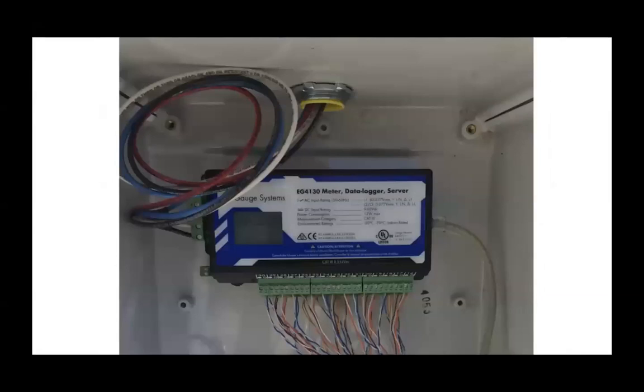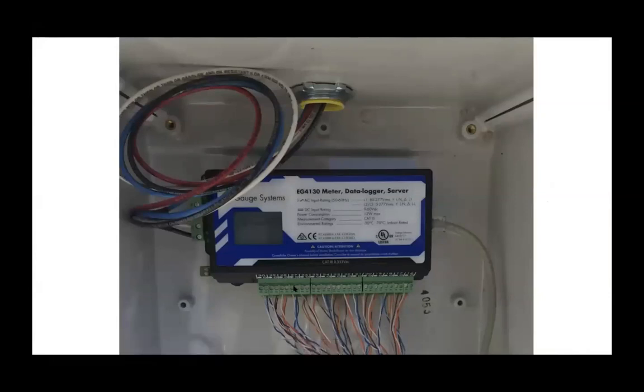This is a pretty typical eGauge installation. The device usually is installed near the building's utility service in order to access the various circuits that are being measured. This particular model is an eGauge Pro model. So you can see down along the bottom here, there are 30 inputs. Each of these inputs leads to a current transformer, or CT, that is measuring the electrical conductors.